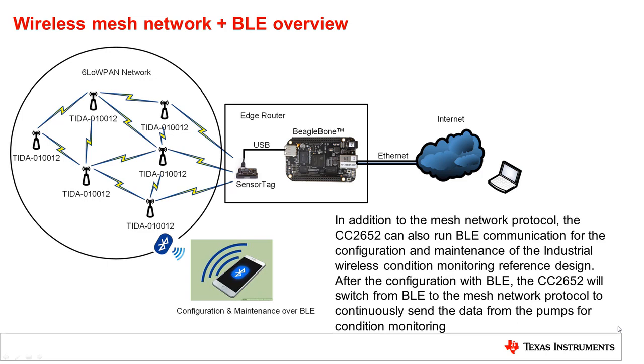In addition to the mesh network protocol, the CC2652 can also run Bluetooth low energy communication for the configuration and maintenance of the TIDA-010012 board. Different vacuum pumps in the factory use different interfaces and data types. Depending on which pump the TIDA-010012 is connected to, it needs to run different protocols on RS232, RS422, or RS485. Using the Bluetooth low energy interface, a smartphone or tablet can configure the TIDA-010012 board for different pump types. After configuration, the CC2652 switches from Bluetooth to the mesh network protocol to continuously send pump data for condition monitoring.